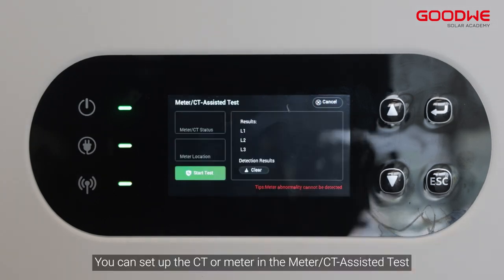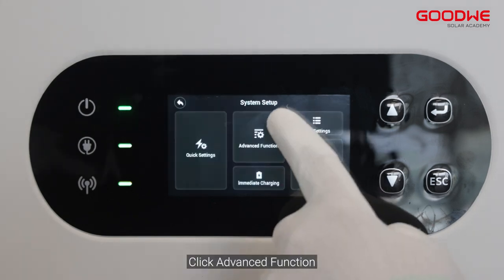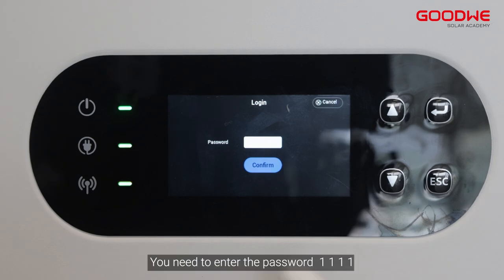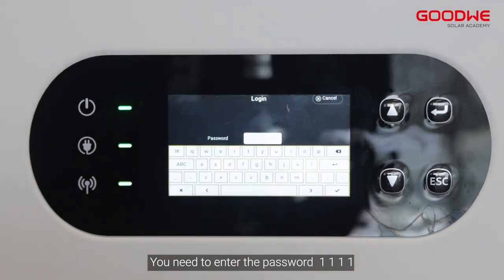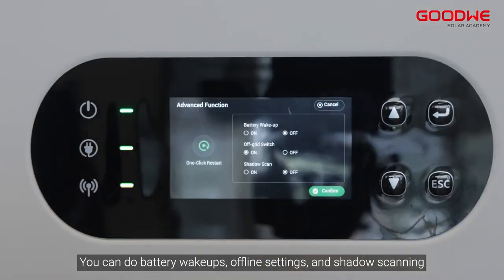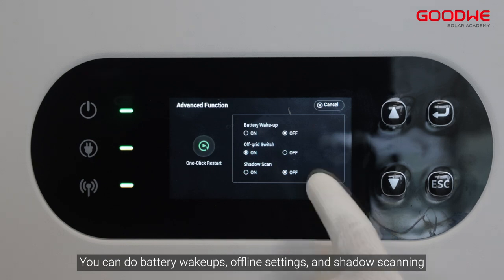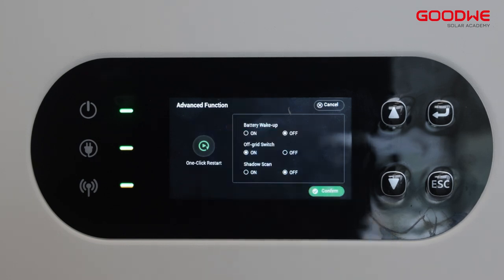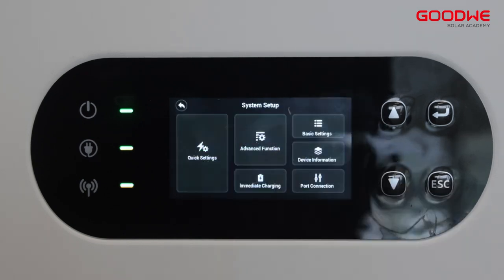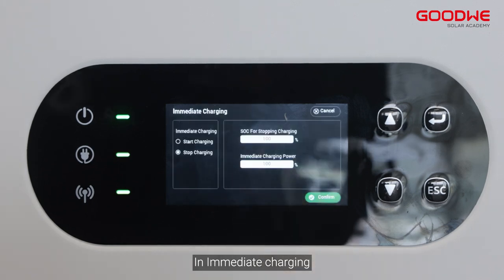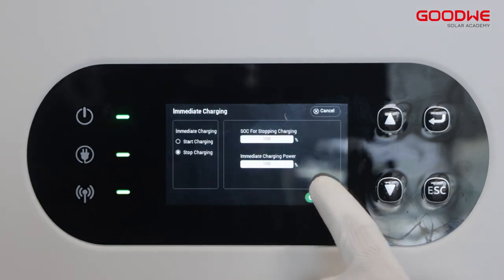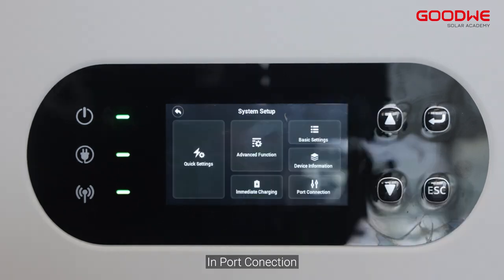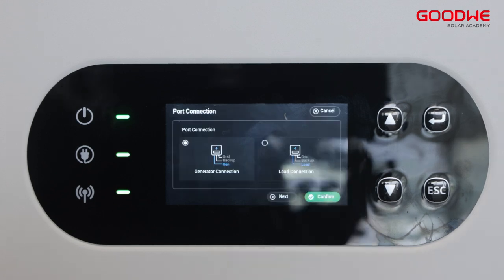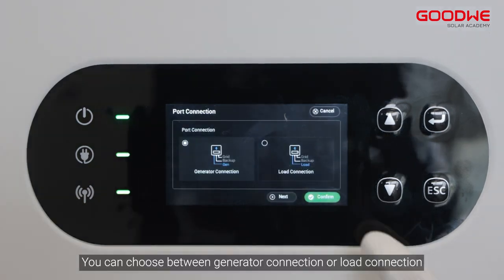You can set up the CT or meter in the meter/CT assisted test. Click Advanced Function. You need to enter the password 1111. You can do battery wake-ups, offline settings, and shadow scanning. In immediate charging, you can set the relevant parameters. In port connection, you can choose between generator connection or load connection.